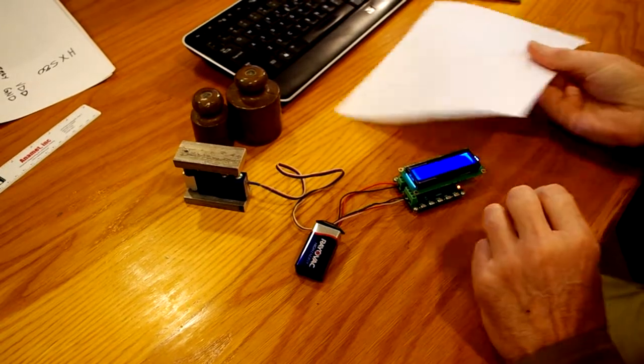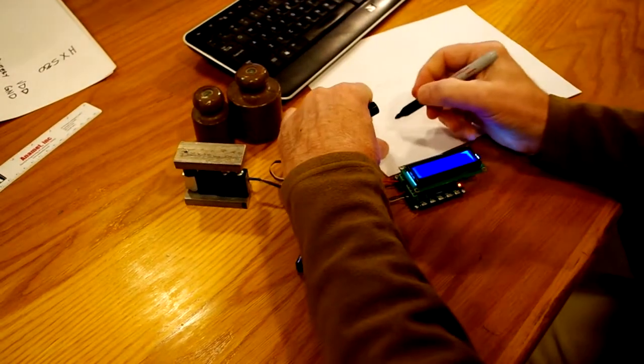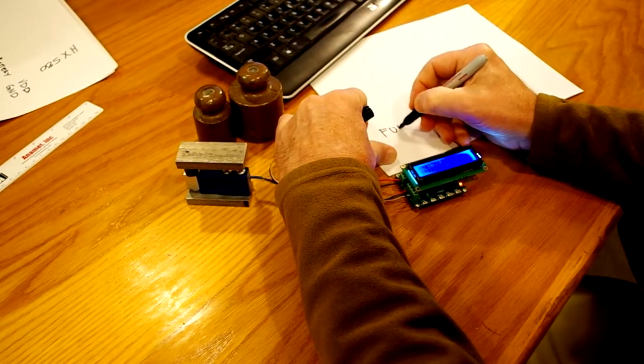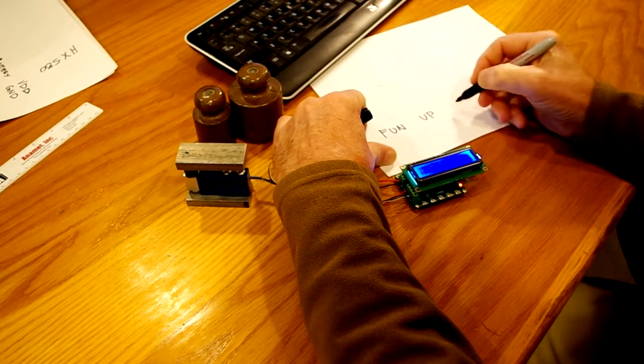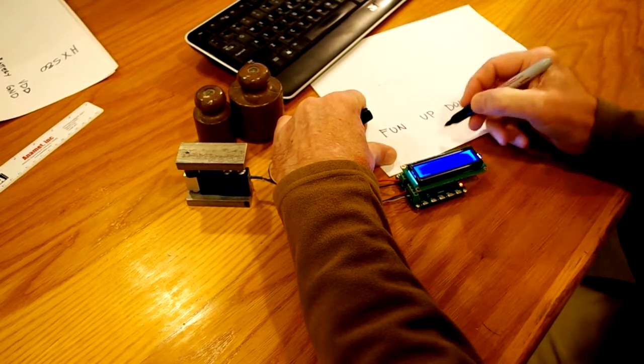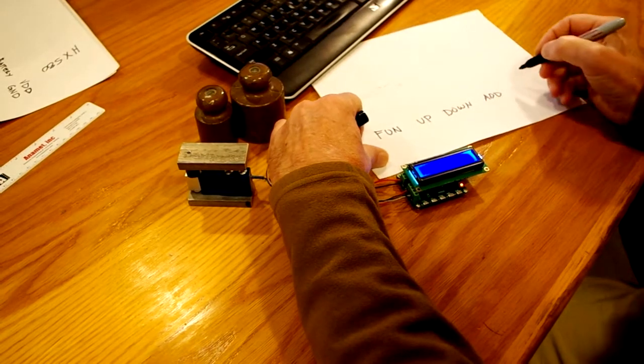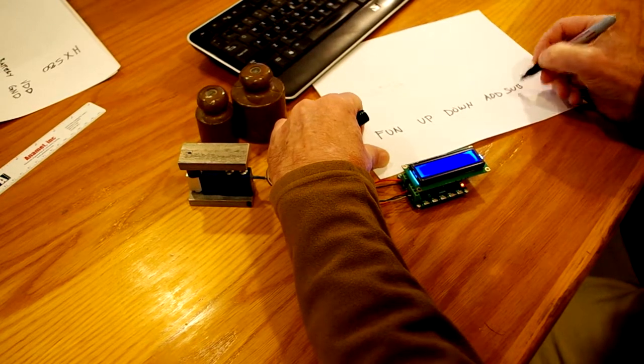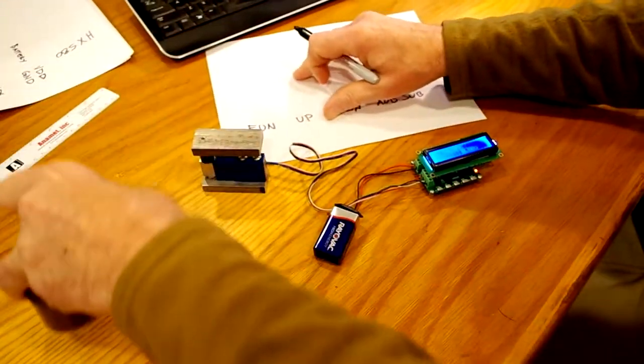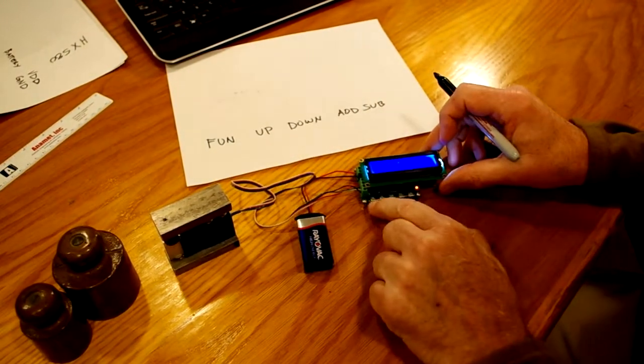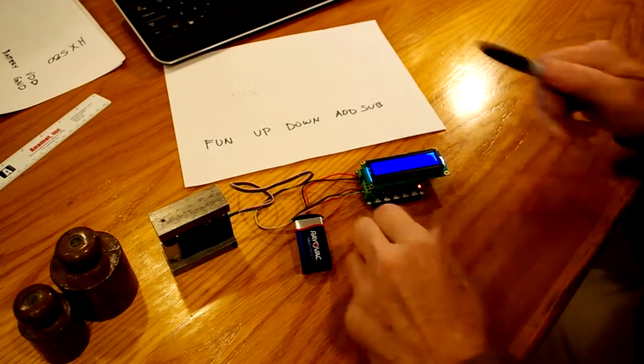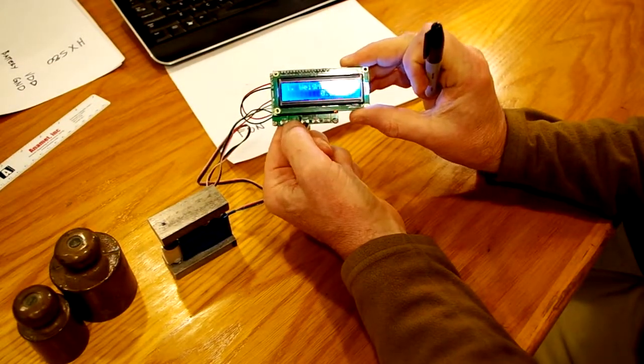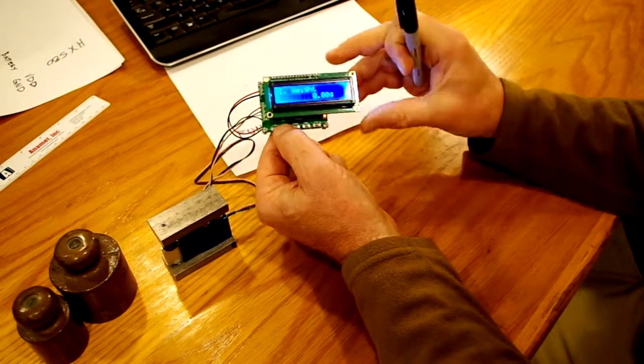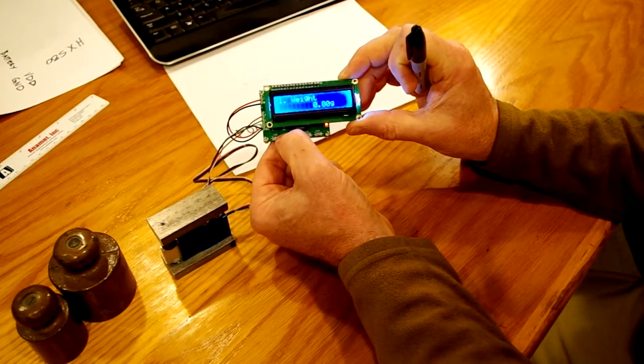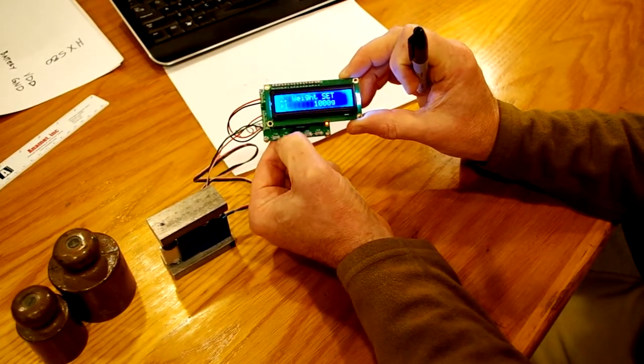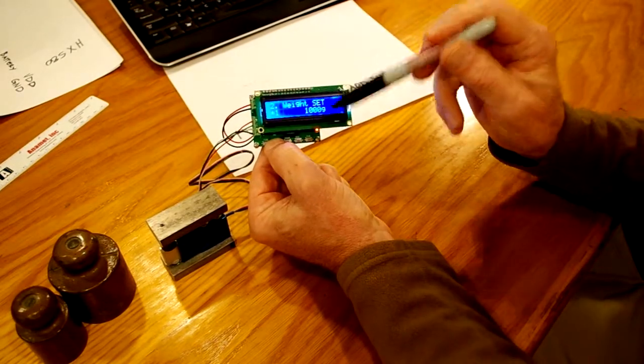Now there's 5 keys that we can use to set this up. There's a function key, an up key, a down key, an add key, and a subtract key. Those are the 5 keys which we have here across the bottom of the unit. Right now it says setting view number 1, which shows apparently the current weight. We hit the up key and it goes to number 2. This is the weight set.